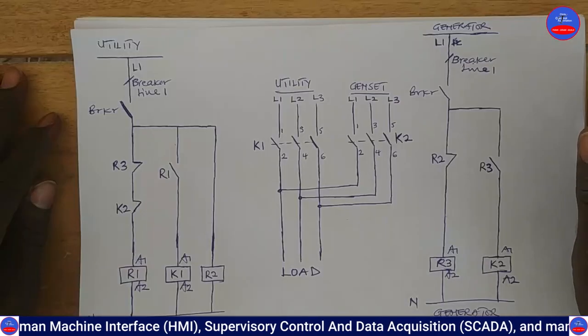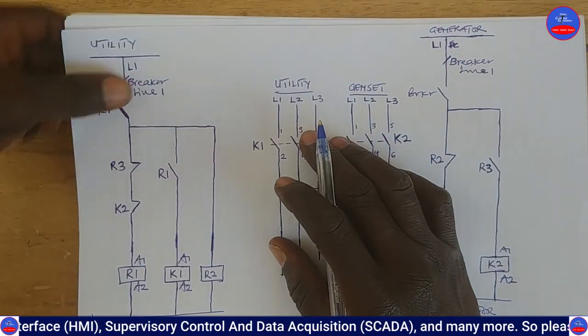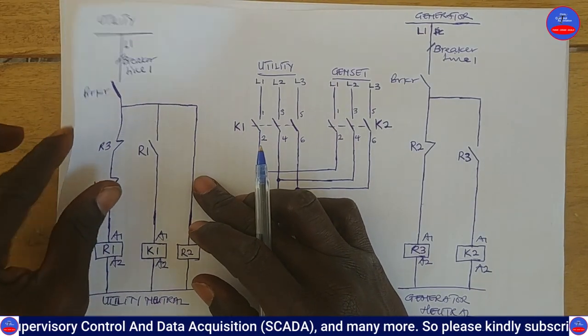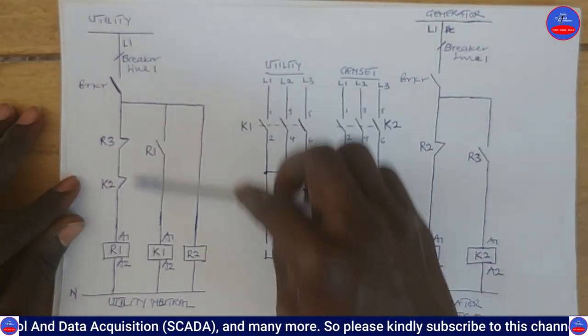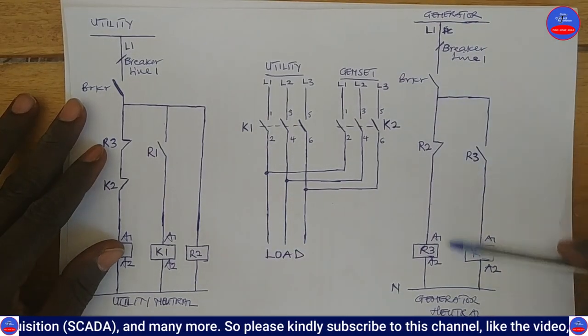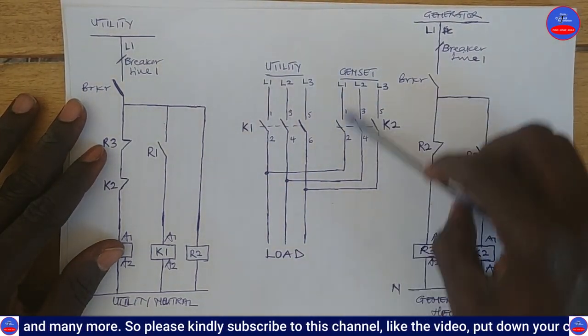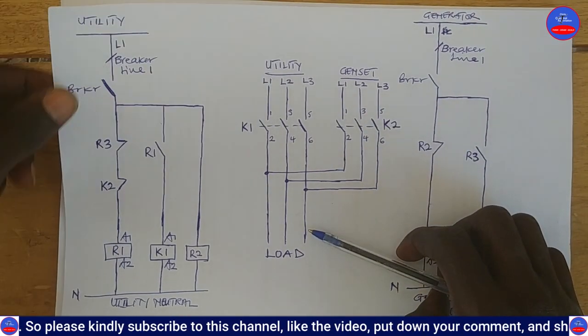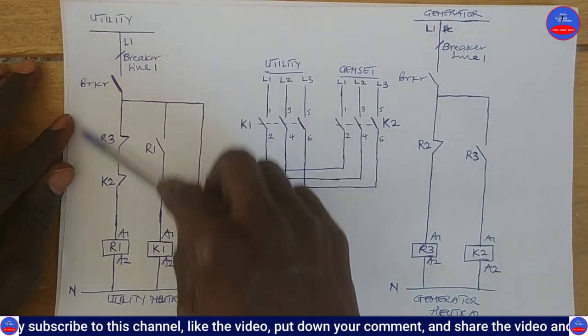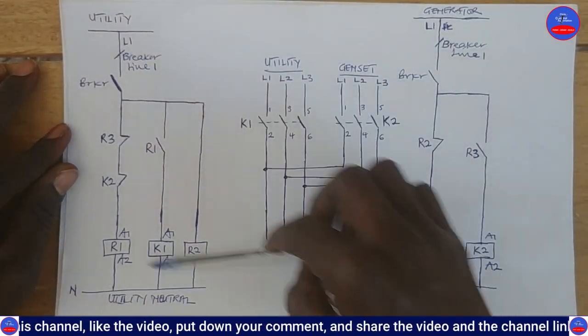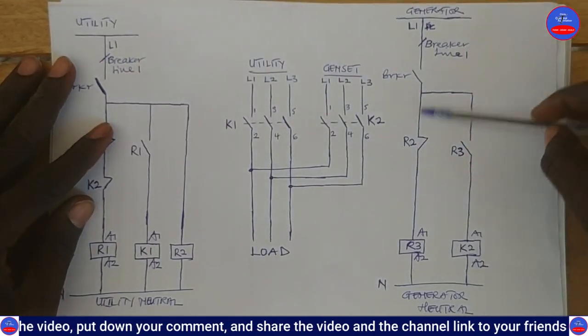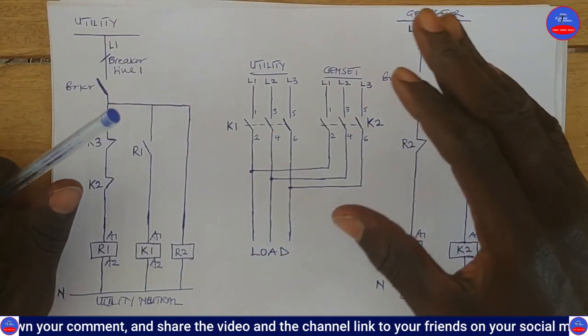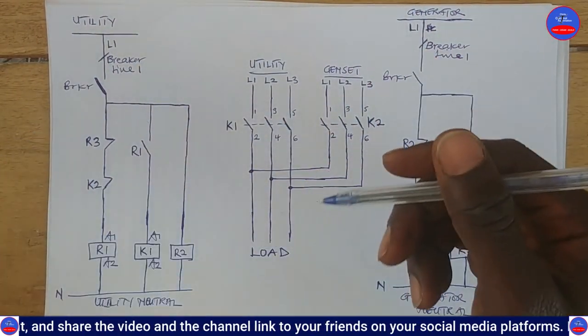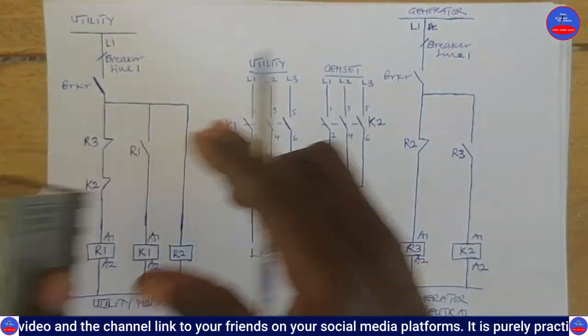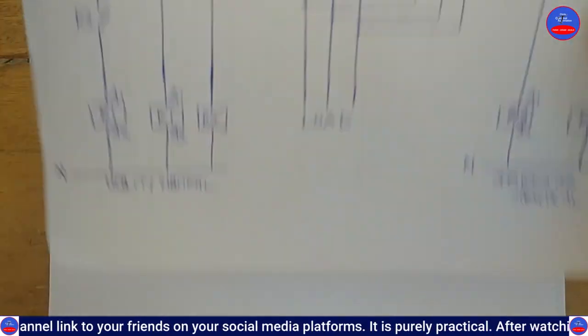So let's get started. Engineers, this is the old diagram. The old one, you have the utility side. This is the genset side, the generator side. This is the power side, the load. But in the new diagram, we are going to maintain the utility side, everything here the same. But in the generator side, we are going to change and add certain things. I told you we are going to include a timer. This is an on delay timer. So let's begin here.